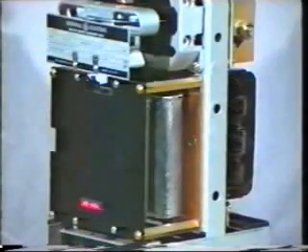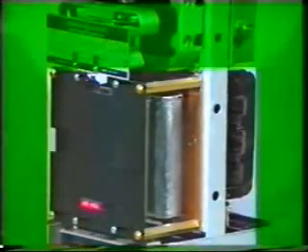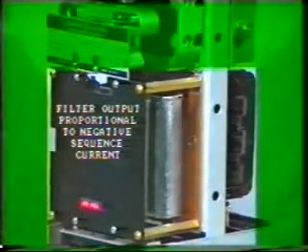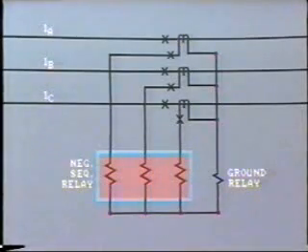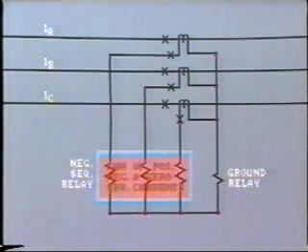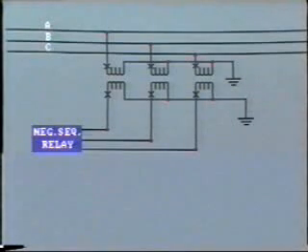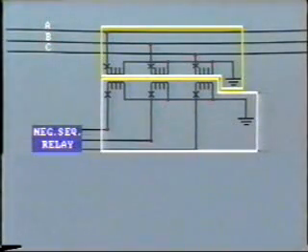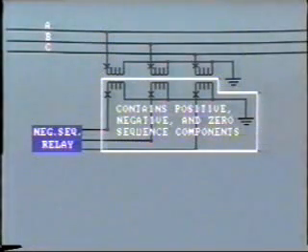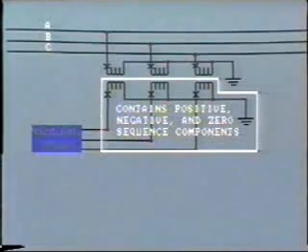For protection, both zero-sequence and negative-sequence relays are installed. Typically, the negative-sequence relay works by comparing voltage or current in all three phases and filtering out negative-sequence components. The current coils are connected to CTs like this. The current flowing through each coil will be the sum of positive, negative, and zero-sequence currents in that particular phase. Note that the zero-sequence components, as they are all in phase, add together at this point and pass through the ground relay current coil. Now let's look at the VT connections. The primary and secondaries are Y-connected with grounded-neutral. The secondary supplies potential containing positive, negative, and zero-sequence components to the relay's negative-sequence voltage coils. This enables the relay to detect the presence and magnitude of negative-sequence voltages.